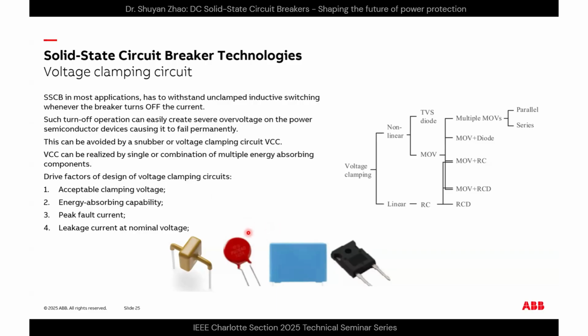This can be avoided by a snubber or voltage clamping circuit, which we call VCC. This circuit can be realized by a single component or a combination of multiple energy absorbing or clamping components. Some driving factors in designing this circuit include figuring out the acceptable clamping voltage, the energy absorbing capability, the peak fault current in the system, and the acceptable leakage current at nominal voltage.